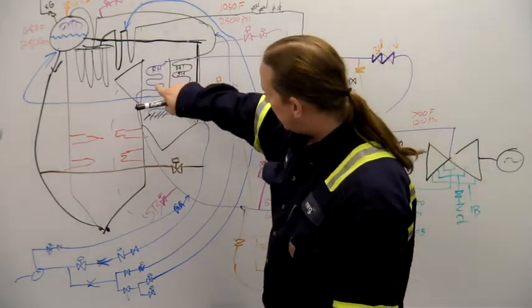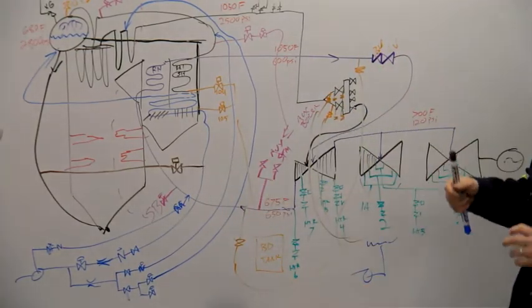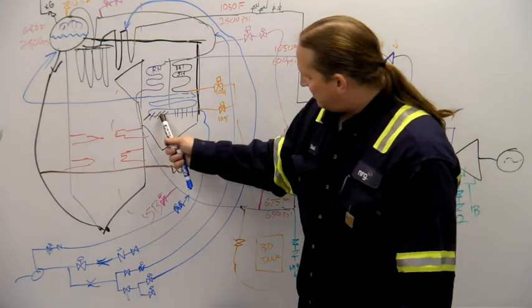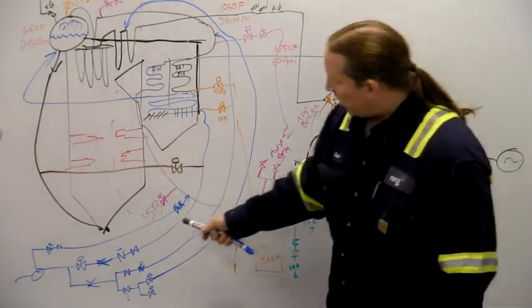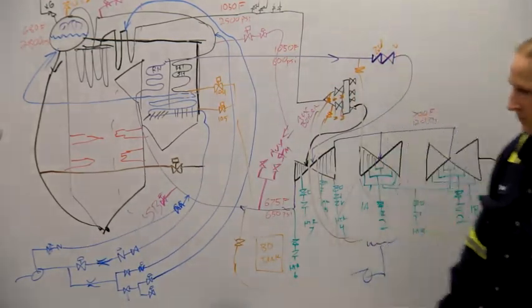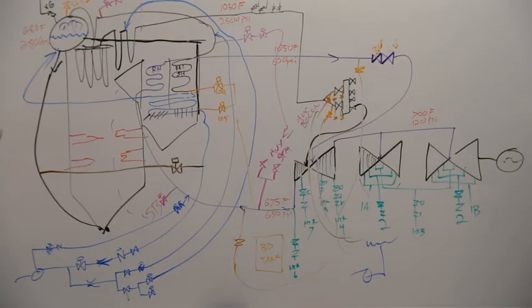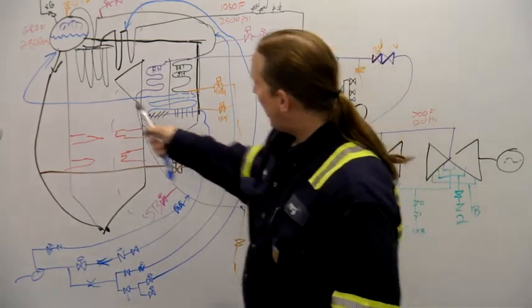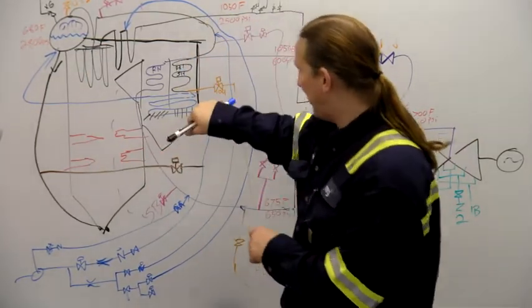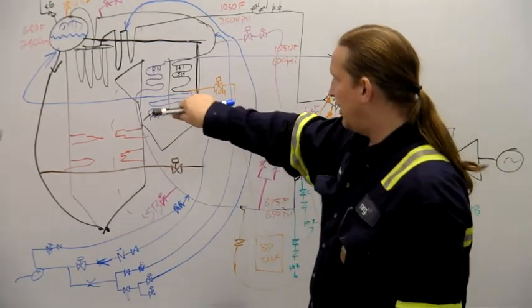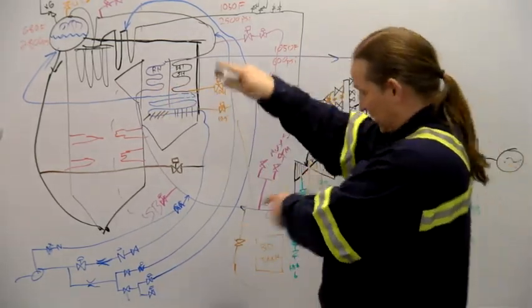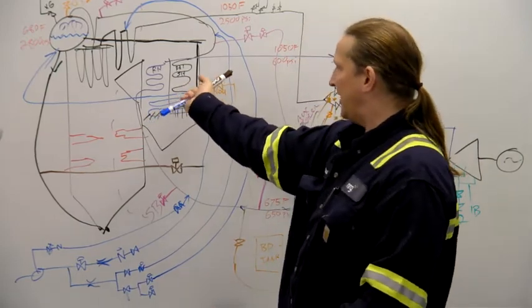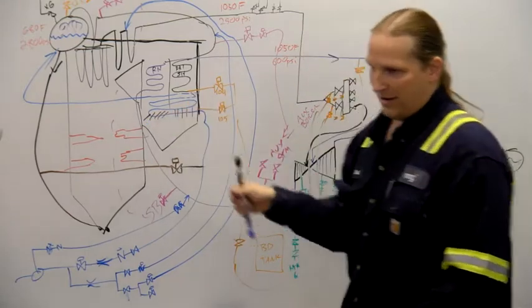These dampers for control are much slower than spraying water into the piping, right? So if a soot blower goes in on the reheat side, it cleans a bunch of crap off of it, now that ash was acting like insulation, right? So you clean it up, and now it starts absorbing a lot more heat, and temperature jumps up. Well, these backpass dampers will fix it eventually, but the system might want to spray some water in there to control it faster. So soot blowers are designed to clean the stuff off the walls and off the pipes. You've got a soot blower at 280 pounds, and it goes through a poppet valve, and it gets a command from DCS, and it's got nozzles that point two different ways. As it goes in, it turns. It's supposed to carve a path, a spiral, a double helix through the dirt. As it goes 22 feet in, hits a limit switch, it's supposed to turn like an extra 90 degrees, so that when it comes out, it carves a separate path, and you get as much cleaning as you can out of the thing.